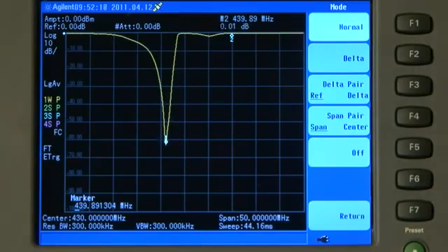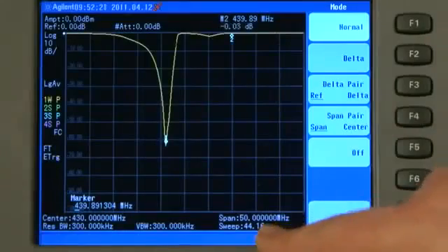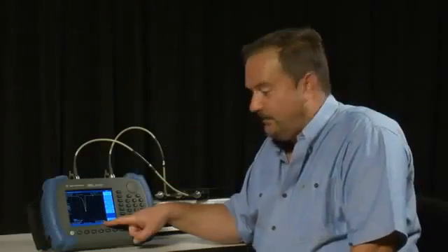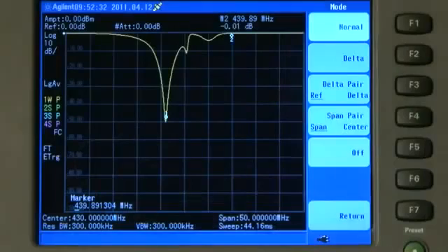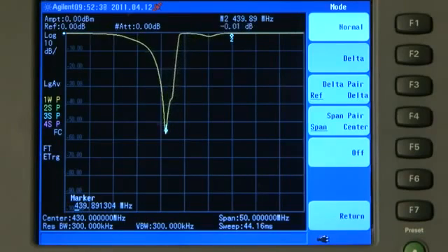And of course, most importantly, we have a very fast sweep time, 44 ms. Quite incredible for a handheld analyzer. So if the filter needs tuning, we can make adjustments to the filter by adjusting the various cavities and tuning it up.